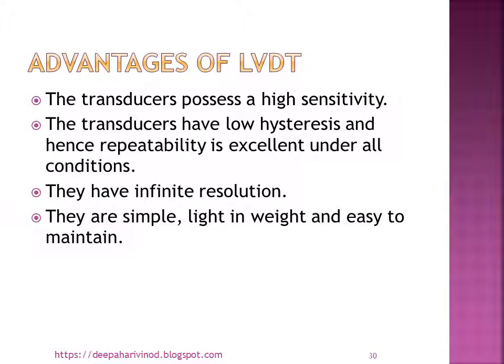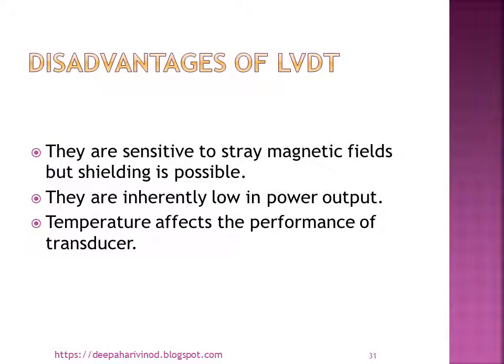Advantages of LVDT. The transducers possess a high sensitivity, have low hysteresis, and hence repeatability is excellent. They have infinite resolution, are simple, light in weight, and easy to maintain. These are the advantages. Coming to the disadvantages, they are sensitive to stray magnetic fields, but shielding is possible. They are inherently low in power output. Temperature affects the performance of the transducer.